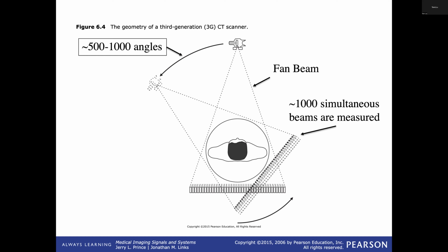And then Siemens actually pioneered a technology where they put brushes on a connecting ring, and all of the data went out over those brushes. And so they could rotate the gantry the same way all the time. And they could rotate it as fast as they wanted, right? Or as fast as mechanically you could rotate the thing. And so now gantries rotate really fast. Well, relatively fast.